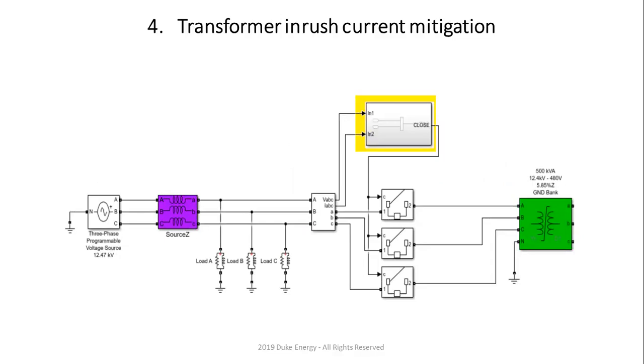When you switch single phase, you are going to have full current going through that neutral CT, which would cause it to trip, right? So when you do your protection and control, you've got to make sure that you don't switch for that, right? So there's something called torque control. You have to torque control for this condition. If you intentionally try to energize the transformer, you actually have to torque control those settings, right? For anything other than the true fault, this neutral CT must not trip, right? So that's part of the security scheme.